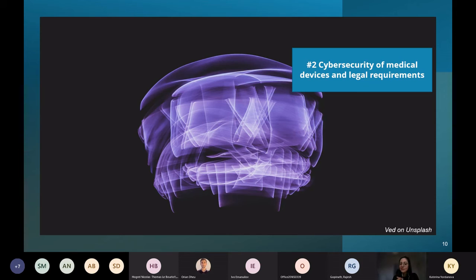So it means that all the different stages of medical device manufacturing need to encompass cybersecurity requirements, security requirements, and this includes the risk management plan for manufacturing a medical device, its risk assessment, its risk control, and also post-market surveillance. And I think these are more or less the most important parts and aspects of medical device cybersecurity, also provided in the Medical Device Coordination Group guidelines.